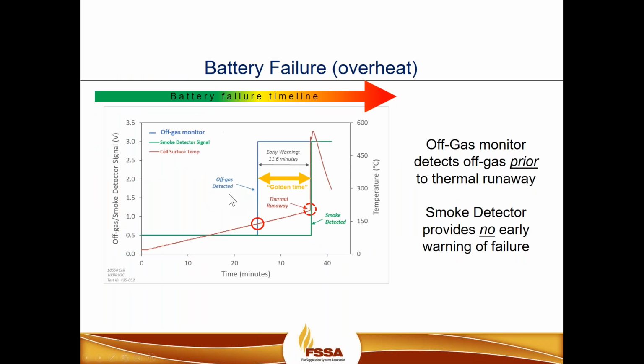Continuing on with the overheating event, this particular test is representative of the UL 9540A that demonstrates the stages of battery failure. Here we're seeing an overcharging of the cell. This purple line represents the overcharging of the cell at 5 degrees Celsius or 41 degrees Fahrenheit over each minute. So we're increasing the temperature 5 degrees every minute per the UL 9540A standards. So as the temperature increases, this is where we're starting to subject the cell to heat or thermal abuse.